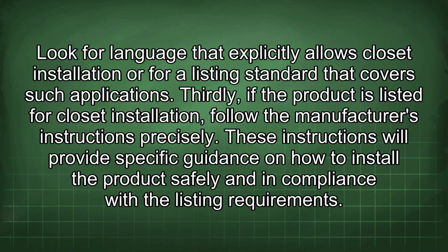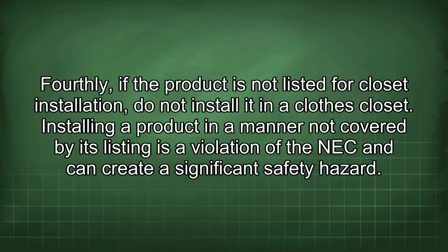Thirdly, if the product is listed for closet installation, follow the manufacturer's instructions precisely. These instructions will provide specific guidance on how to install the product safely and in compliance with the listing requirements. Fourthly, if the product is not listed for closet installation, do not install it in a clothes closet. Installing a product in a manner not covered by its listing is a violation of the NEC and can create a significant safety hazard.